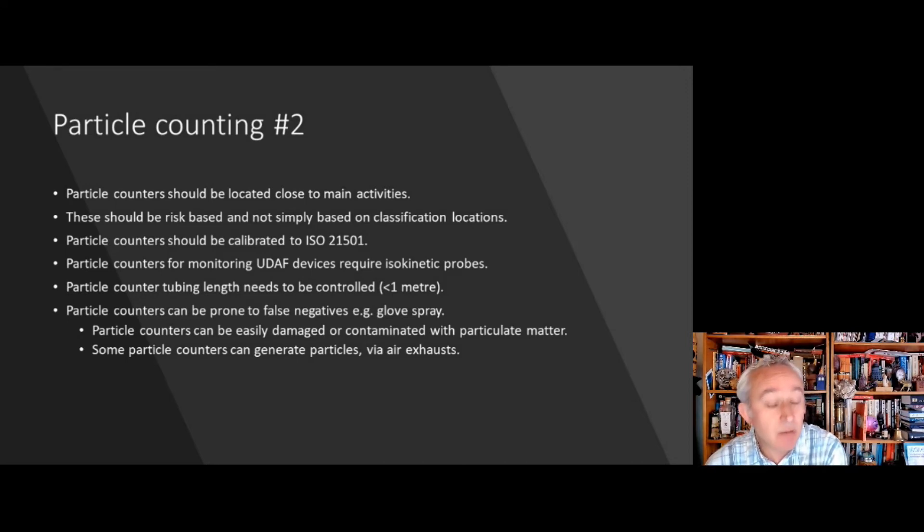Particle counters should meet and be calibrated to ISO 21501 standard.